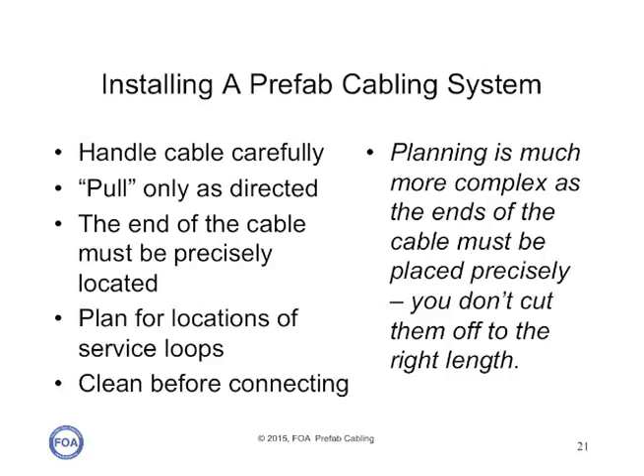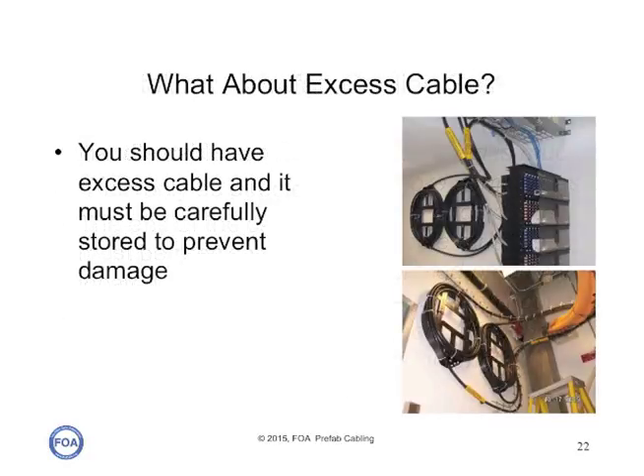And before you connect any of these connectors, you have to clean them. Planning for the installation is more complex than you think, because the ends of the cables must be placed precisely. You can't cut them off to the right length. As part of your planning process, locate where you're going to store your excess cable and how you're going to do it, so you'll know where to leave excess length and how to spool it up, get it out of the way, and protect it.